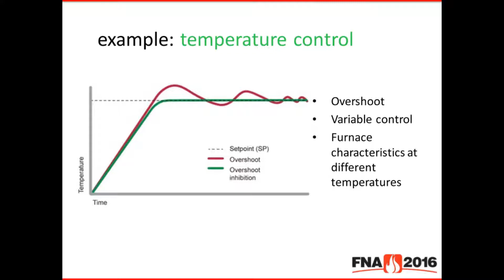But if you've got the derivative equation running, that actually looks at that interruption and is trying to pick out what's the rate of change of my error and how is that going to affect my speed of getting to zero. So if it sees that I'm going to minimize that to zero very quickly without me putting any more output in, it's not going to do anything. If it says, okay, there's been a big change and I need to put in some extra power, that's when the derivative acts on that.